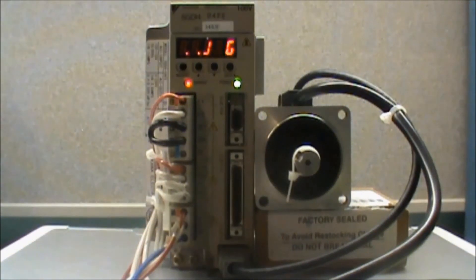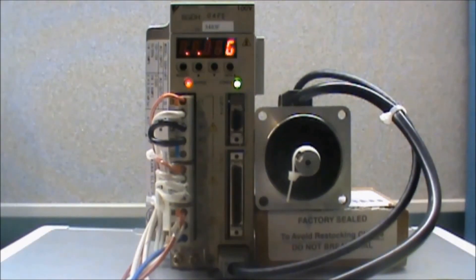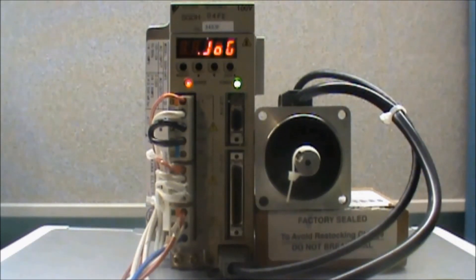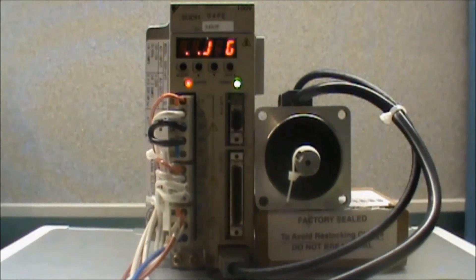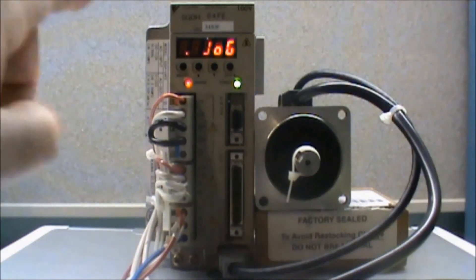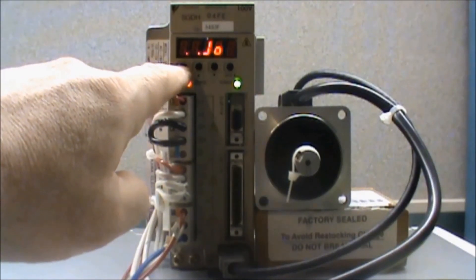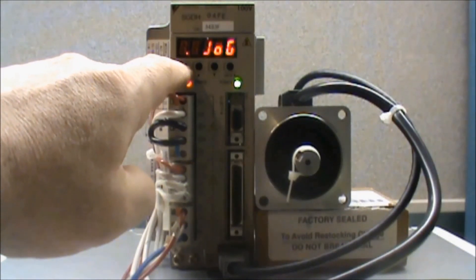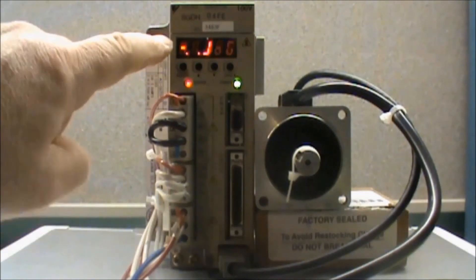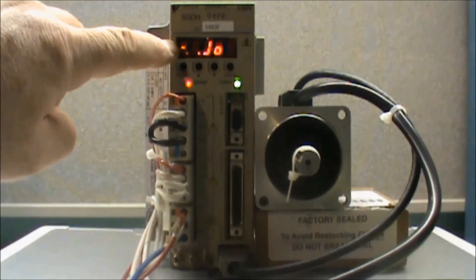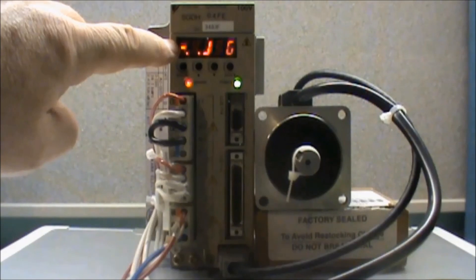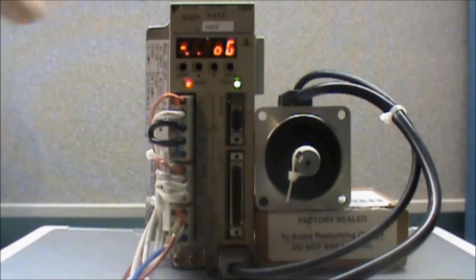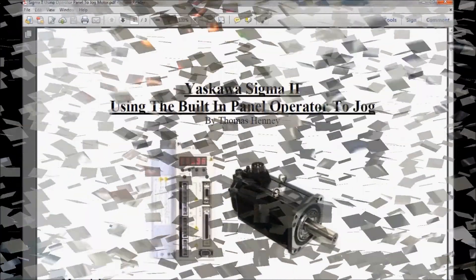Now I need to disable the jog function. To do this, I can press and hold the data button. And that will take me back to the auxiliary function mode and remove power from the motor. Or I can press the mode set button. This is the button on the left. And it will leave me in the jog display. But it will also put the amplifier back into base block and remove power from the motor.